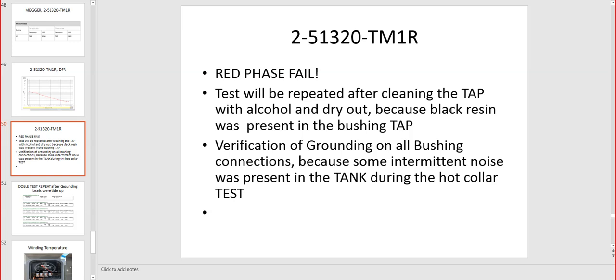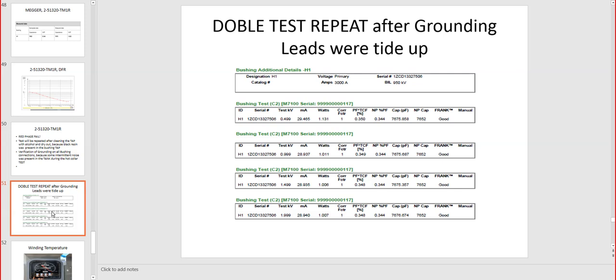As we said, we cleaned the tap, like the bushing, with alcohol and dried it out. We cleaned the black resin that was present around the bushing. Verification of the grounding on all bushing connections. Some intermittent noise was present on the tank during the hot collar test, so you can see that on the actual signals that there was an intermittent connection, so a bad connection with the grounding.